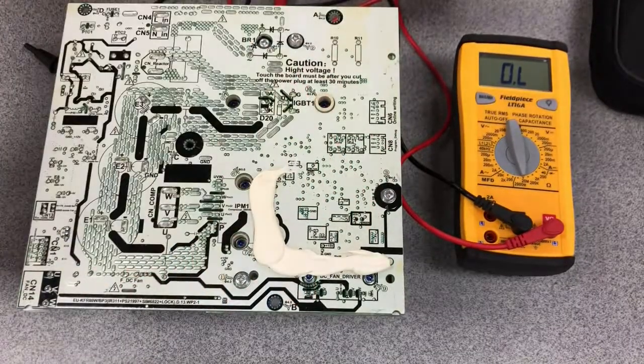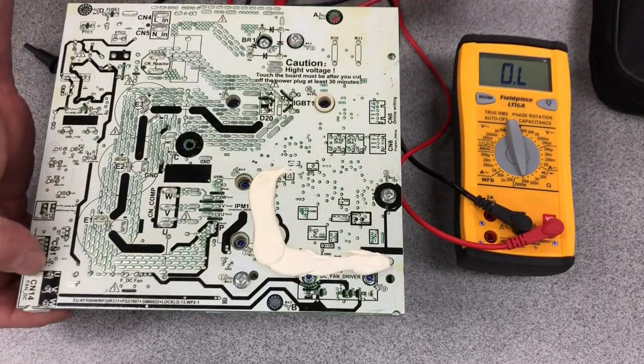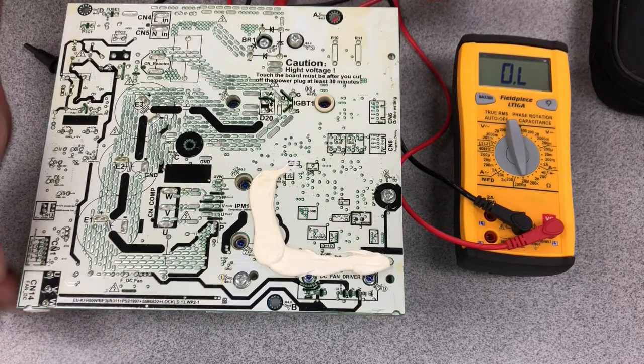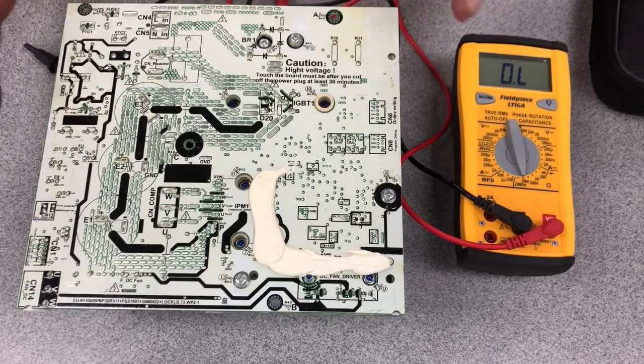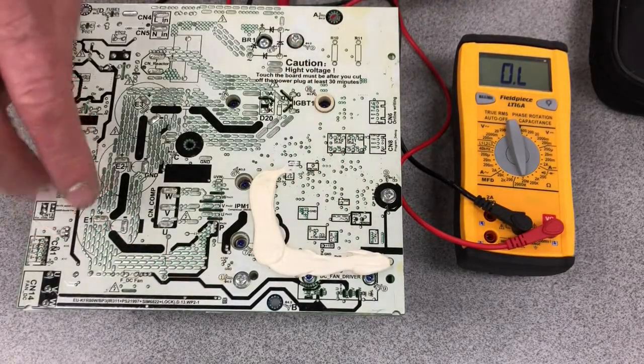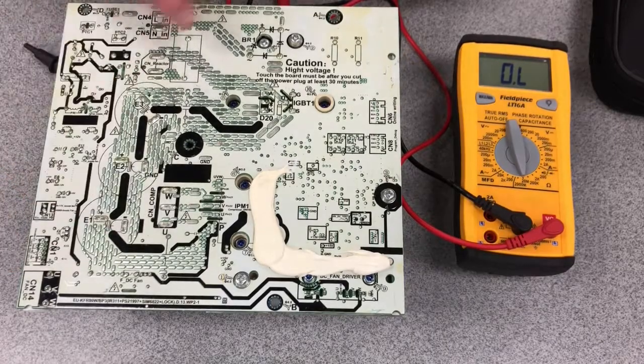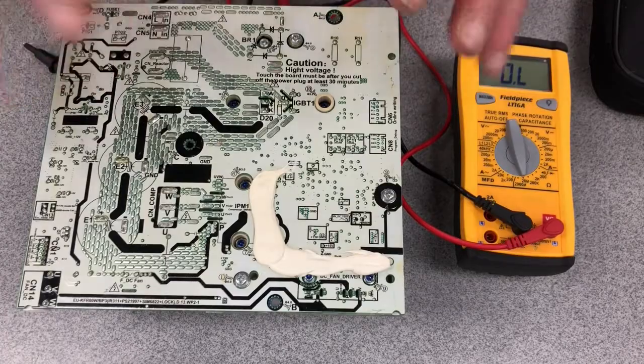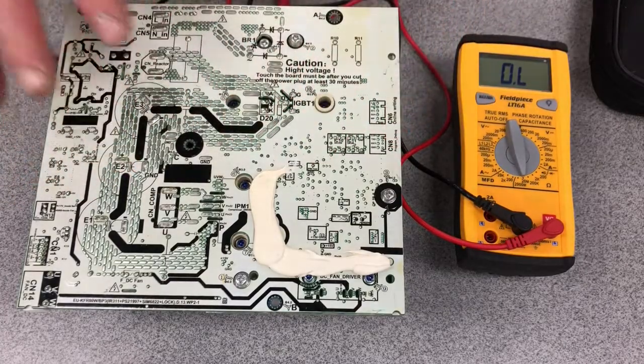That's telling us that the IPM module is good. If I look over in the corner here where my condenser fan motor terminals are, U, V, W, I can do a test there the same way. This indicates that yes, my transistors are working. When I checked my voltage here, I had my 300 volts, which indicated my diode bridge is working. So all indication here is that this module is good.